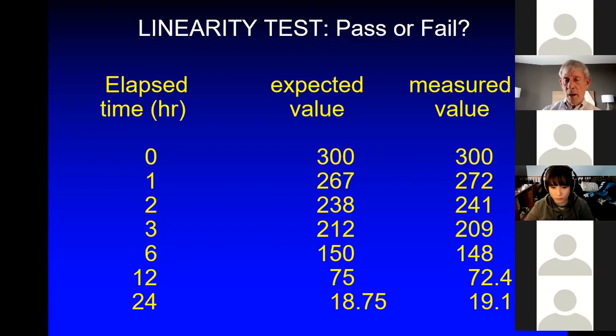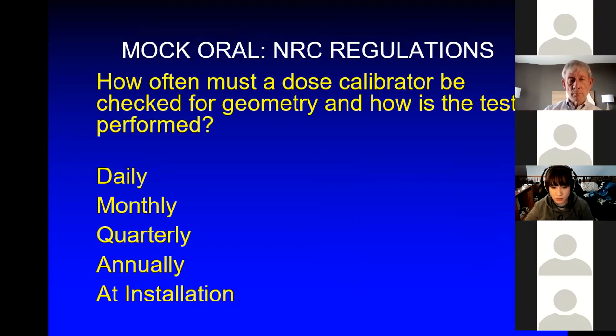How do those numbers compare? Are they all within 10%? Pass. Pass. Definitely a pass. They're all well within 10%. How about geometry? There are actually 3 times we have to perform a geometry test.